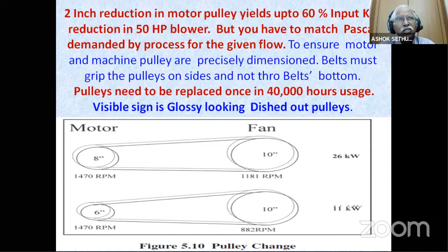This is an excellent case study which we have presented to all the AC majors, AC OEMs, to the industry, and even to the government. Any industry running variable torque loads like air handling units or air washers can achieve 30 to 40% savings with a VFD and a resized speed ratio between pulley and machine, motor and machine.